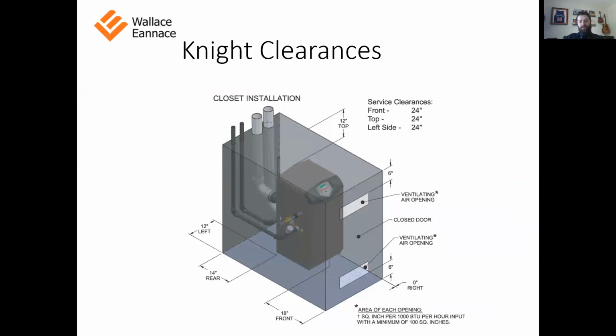So first, clearances for a Knight. As you can see here, you got 14 inches in the rear, 18 up front, 12 at the top, and 12 on the left side. You only need one side. The connections are only on that left side of the boiler facing the front of it. So not a lot of space to get these going. You do need to put these on a hard floor, concrete housekeeping pad usually. You don't want this on a wood floor, for instance. That's probably the only restriction with that.